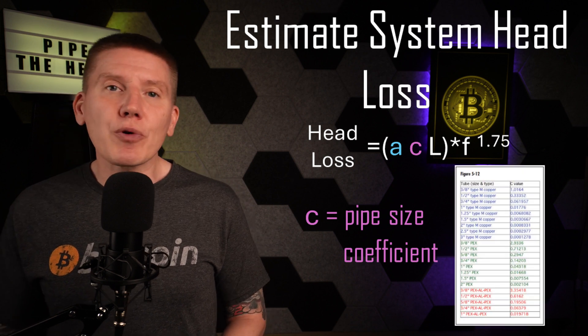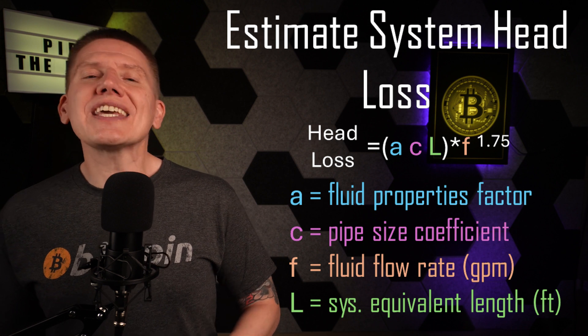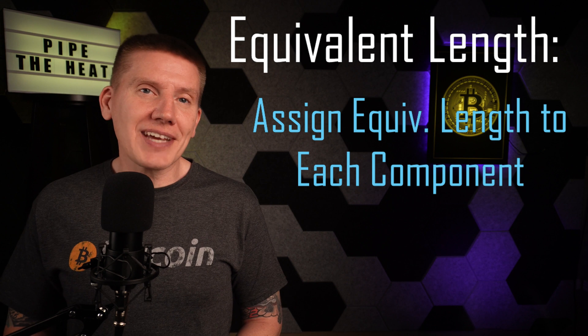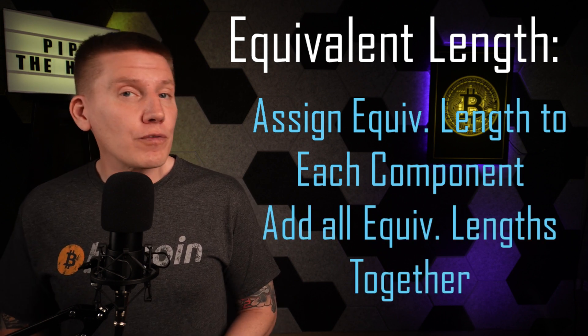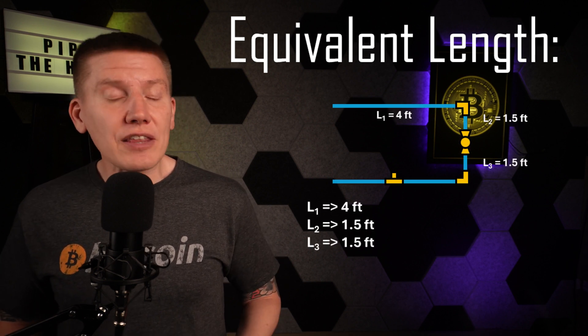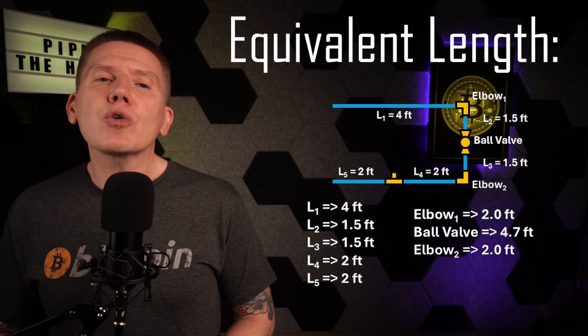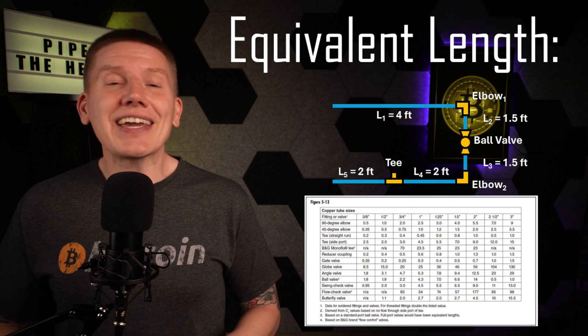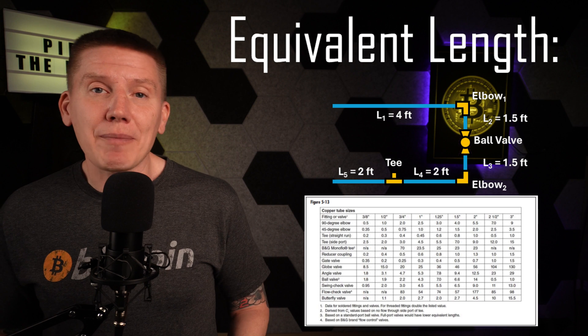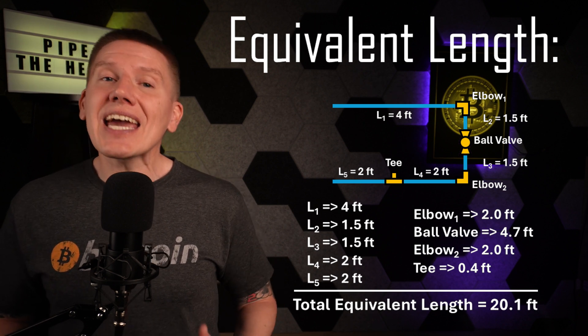C is a pipe size coefficient — the hydronics articles have a table with this information for a range of common pipe sizes and types. F is the fluid flow rate measured in gallons per minute. And finally, L is what is called the equivalent length of the hydronic circuit. This equivalent length is a really easy way to account for the effect of all of the different piping and fittings. The idea is to take all of the different components and assign an equivalent length to each one of them, and then add all of those equivalent lengths together to get the total equivalent length of the entire system. For straight piping, the equivalent length is just simply the length of the pipe itself. But for elbows, valves, and other fittings, you have to account for the added resistance to fluid flow, and so you can look up the equivalent length for each component. The Caleffi articles have a handy table that will give you the equivalent length for a bunch of common fittings. After adding up all of the equivalent lengths of all of the components, the total equivalent length is entered into the formula to get the head loss of the system.